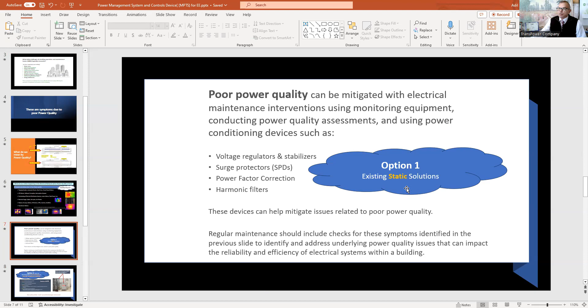Today, no building has a static load. These devices work well when you have static loads, for example a motor running 24 hours a day at the same consistent load. But today everything is controlled by computers and automation—all your loads, temperature, usage, lighting, and air conditioning in the building. So static solutions may be good for static loads, but with today's changing load conditions, you need something to deal with it.